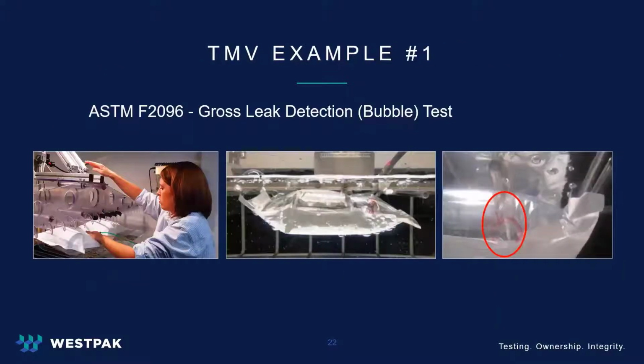Let's briefly walk through gross leak detection testing and what a TMV looks like. Consensus standard ASTM F2096 details gross leak testing. It is a sterile barrier test that involves submerging a sample beneath the water, pressurizing it, and looking for any breaches that would compromise the sterile barrier.